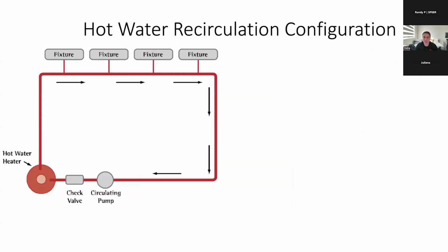So how you configure the loop is just as important as how you operate the pump. The guidelines in WaterSense say, number one, you want to minimize the piping. And just a few weeks ago, the New York Times had a cover story that, of all things, had to do with research on reducing pipe size in plumbing and creating new codes for minimizing pipe sizes, which I thought was an interesting story for the Times to run. But the heat losses in a distribution system are largely a function of the surface area of the pipe. So if you can reduce the piping, you're going to minimize the heat losses.